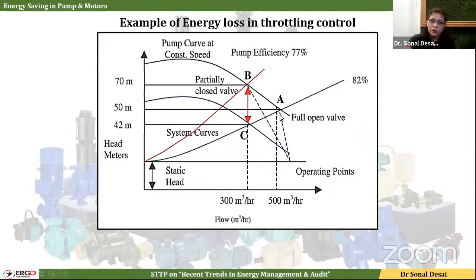Now when I put a throttle in the pump, I make the pump operate at point B. At point B, my flow is reduced from 500 to 300 meter cube per hour and my head increases from 50 to 70 meter. As I just said, I'm not going to utilize this head, but my flow requirement is matched. So as my end requirement is matched, I should operate there. But when I operate the pump at point B, pump efficiency is 77%. So that is a 5% loss, and if you calculate the equivalent shaft power and then electricity, it will be a huge loss. So rather than operating at point B, what is recommended? Have the pump operated at point C, which is again on the same system curve. It will give me a lesser flow rate, but with lesser head.